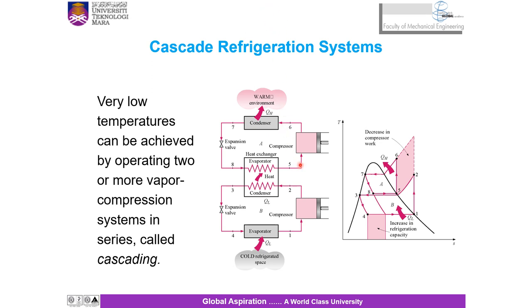Some industrial applications require moderately low temperatures, and the temperature range involved may be too large for a single compression refrigeration cycle to be practical. A large temperature range also means a large pressure range in the cycle, leading to poor performance for a reciprocating compressor. Those are the setbacks if you want a very low temperature.